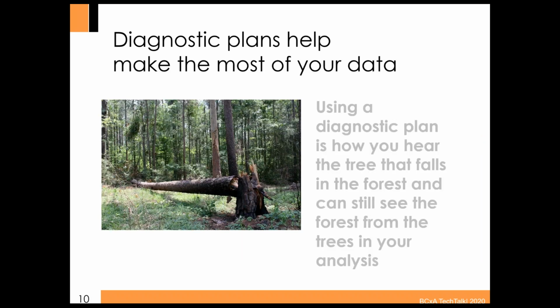Okay. Maybe just blowing this up to the bigger picture and looking at this a little bit differently. I see the diagnostic plan really as making the most of your data. One analogy I think is good here is, if a tree falls in the forest and no one hears it, did it really fall? The diagnostic plan and using that data makes sure that we hear every tree that falls. Just because that damper is not working correctly and no one was there to see it, it's still having an impact on performance. And through that manual check or an automated check, you're ensuring that you're able to see that.